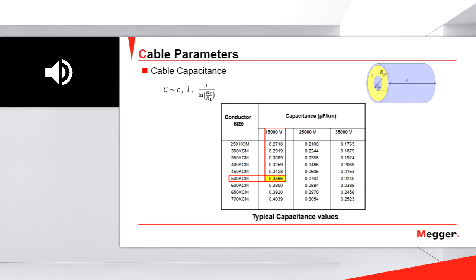So if you have a really very long cable, you will need a fault locator with a big capacitance. So this parameter is very important. If you have a very long cable, but the thumper or the fault locator that you have does not have enough capacitance, you will not be able to find the fault. This is a very important parameter.